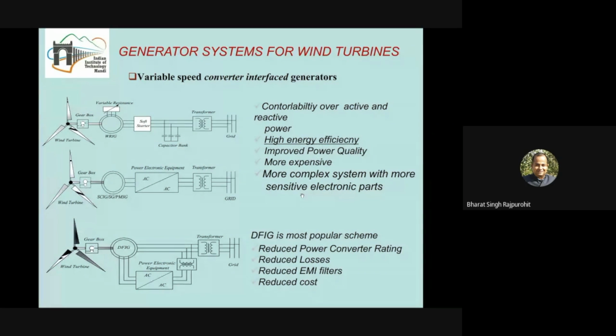In this case, the name is doubly fed because the generator is connected through a stator as well as through a rotor. So it means it can be fed from double side. That's why the name is doubly fed. This doubly fed induction generator has a rotor which is connected with power electronic equipment. The bigger advantage between the middle and the bottom scheme is that in the middle scheme the power electronic equipment is connected at the stator and has the same rating as the generator, but in the rotor DFIG scheme, the power electronic equipment is connected in the rotor where the power processing is low, and hence the rating of this equipment is low. This is why the overall DFIG scheme becomes more economic as compared to the middle scheme.